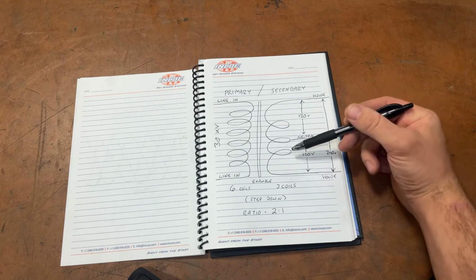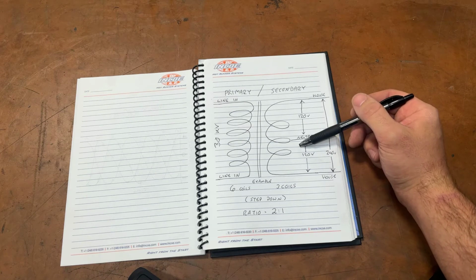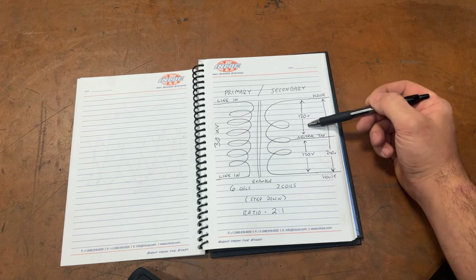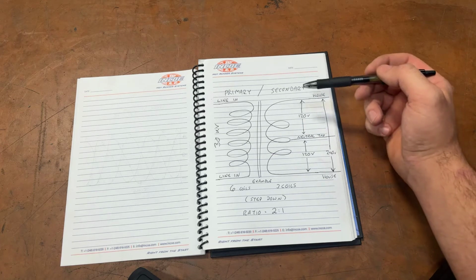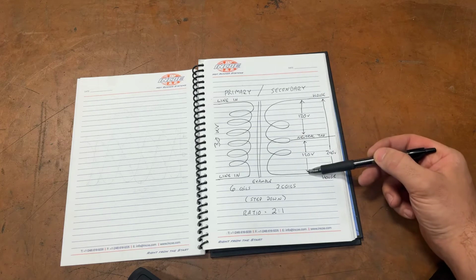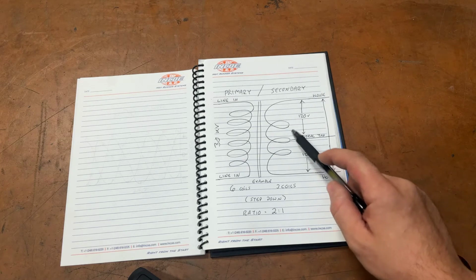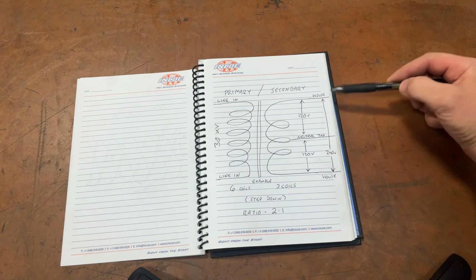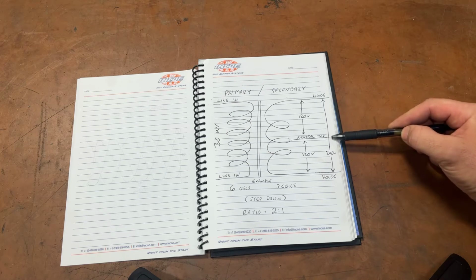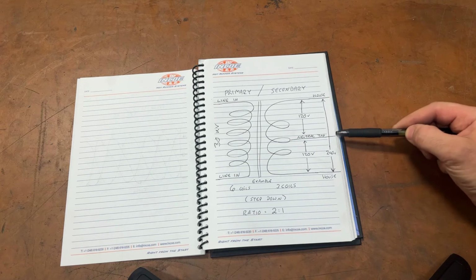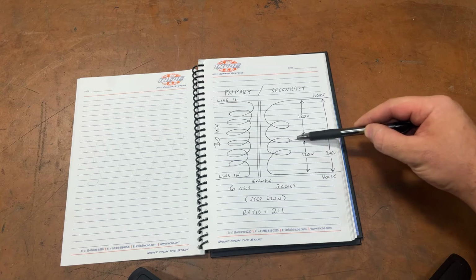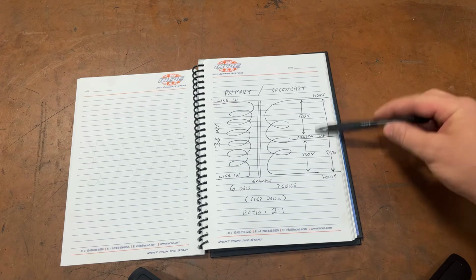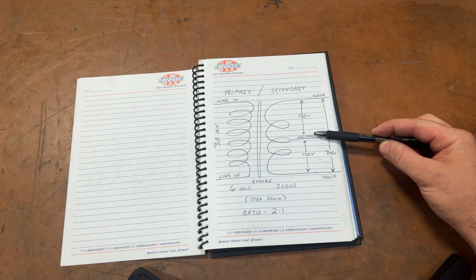But the cool thing about this, a lot of people don't know, the 240 volts that goes to your house, it's no different than the 120 volts that goes into the regular outlet in your wall. It's just where you tap onto the secondary side coil. See this illustration here, the 3 lines that go to your house from the pole, one line is the top of the transformer. Your neutral bar that ultimately hooks up to the ground and bonds inside of your house is the center tap. That is your potential area. So you have to have a 0 somewhere for this thing to reference to give you power. And this is your other bus bar.